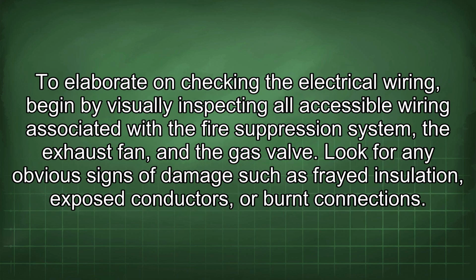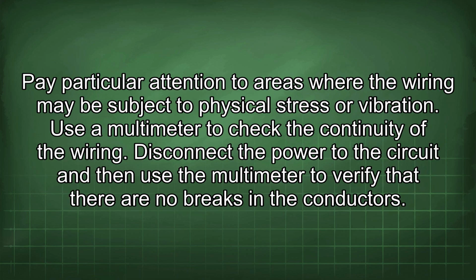To elaborate on checking the electrical wiring, begin by visually inspecting all accessible wiring associated with the fire suppression system, the exhaust fan, and the gas valve. Look for any obvious signs of damage such as frayed insulation, exposed conductors, or burnt connections. Pay particular attention to areas where the wiring may be subject to physical stress or vibration.